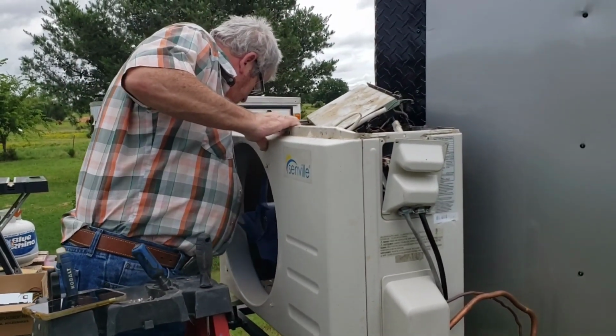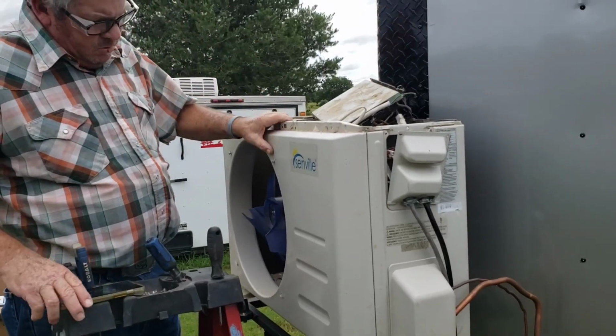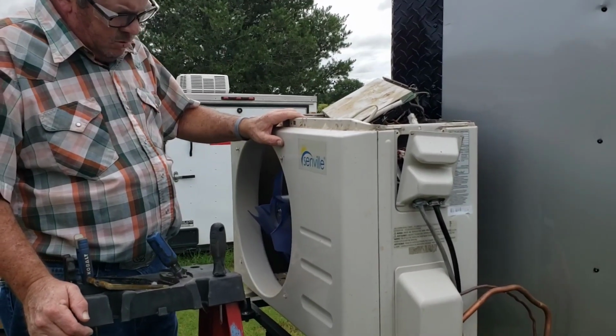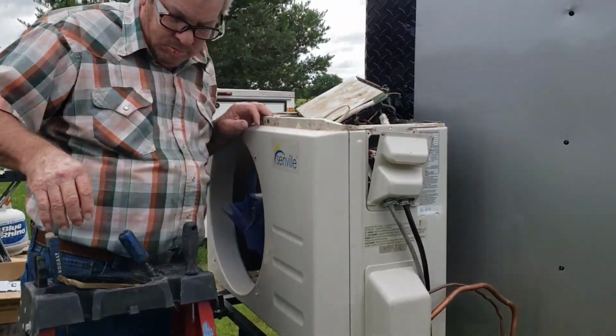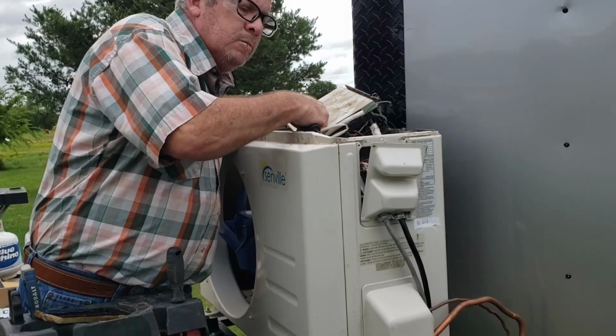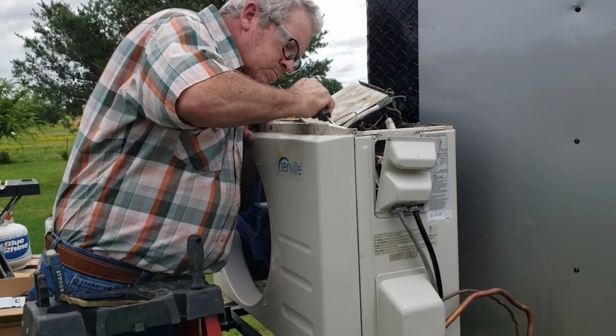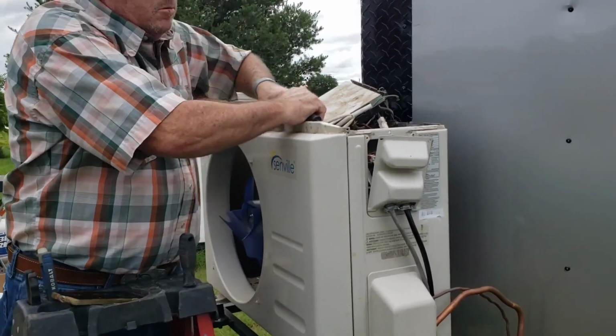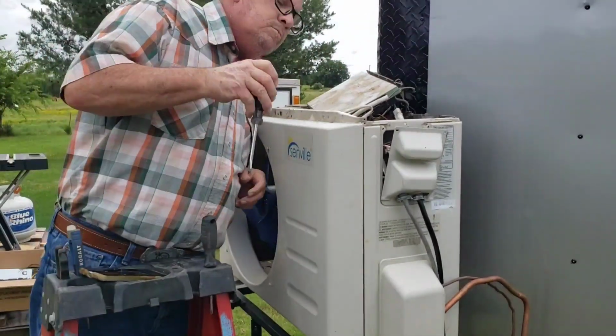He did tell me, however, that once we had to completely unplug the unit, we pulled the top off, and now he's got that one not unhooked, but he's got it kind of pulled out there, as you can probably see, I hope. And he did say that the Senville tech man said that once we hook all this back up, it will take 1.5 to 2 hours before the unit will kick itself back on. It has to reset the new control panel. So that's really about all he told us about the new one. And he just kept saying it was a very easy install.